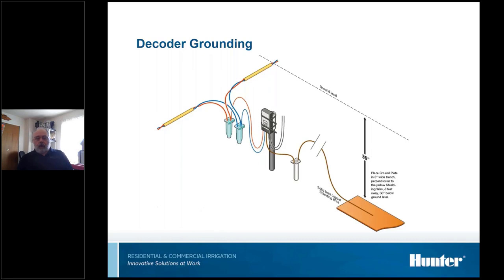The one thing about this diagram, though, that's wrong is this. Remember I told you to make nice, smooth, sweeping turns. Well, that's about as opposite of a smooth sweeping turn as you can get when you stick them two wires in a wire nut. They're opposed to each other. What you really want to do is use one of these. They call these things split bolts. You take the two wires, put them in that opening, and then just tighten the bolt on itself. A little bit of dielectric grease goes a long way in one of these, just to make them last longer. But split bolts are far preferable to using wire nuts and grease packs on grounding.